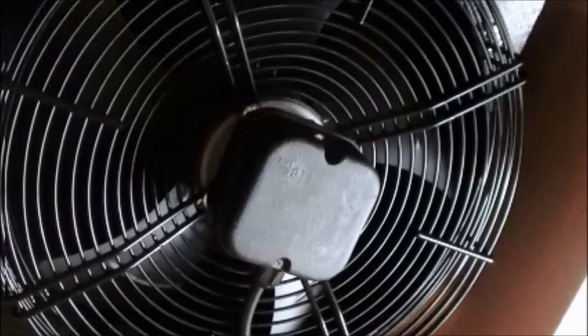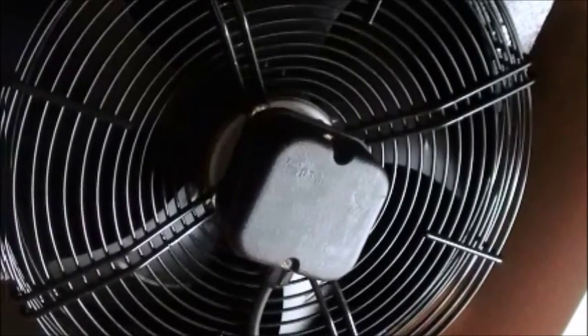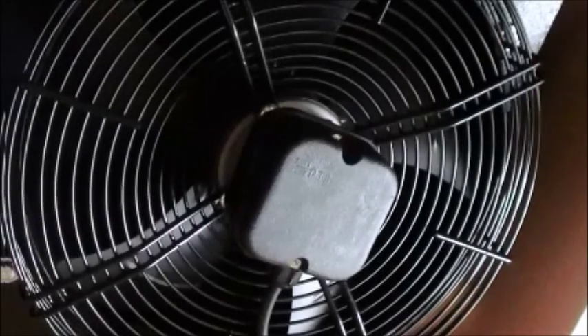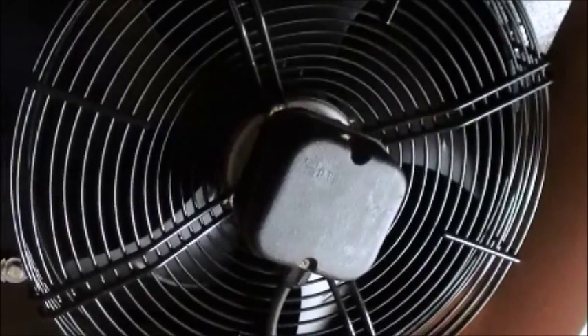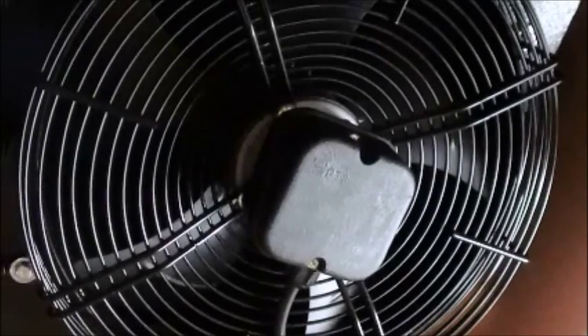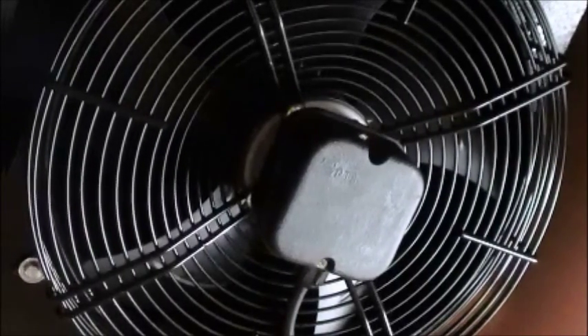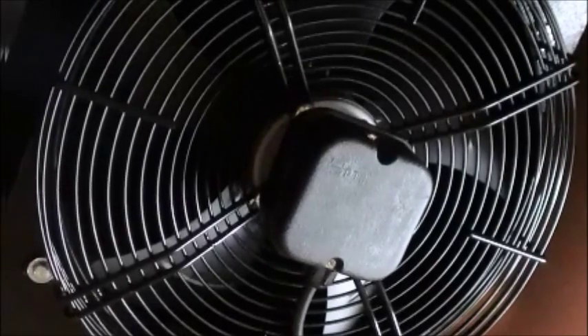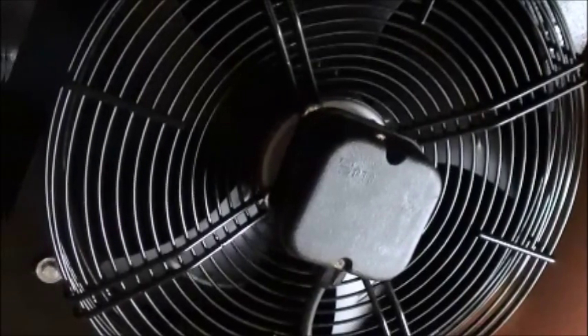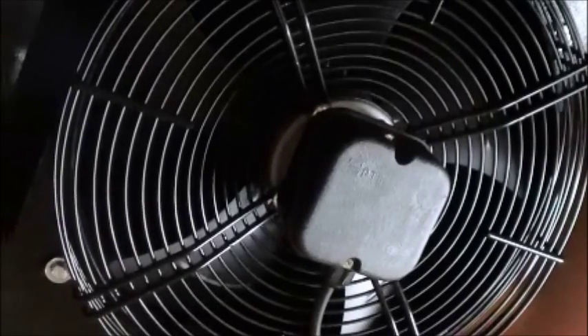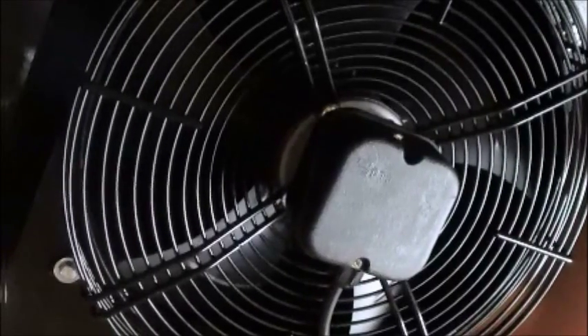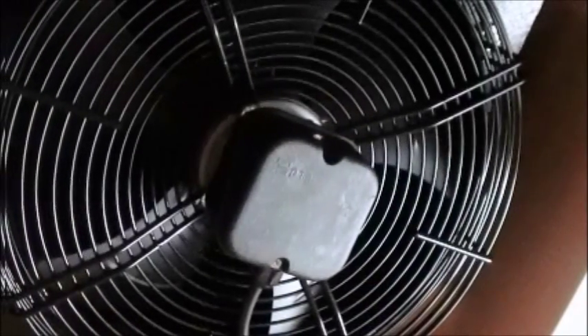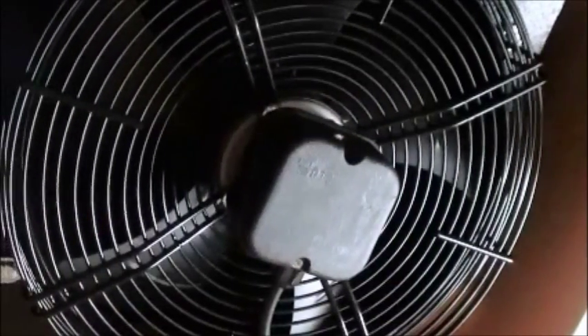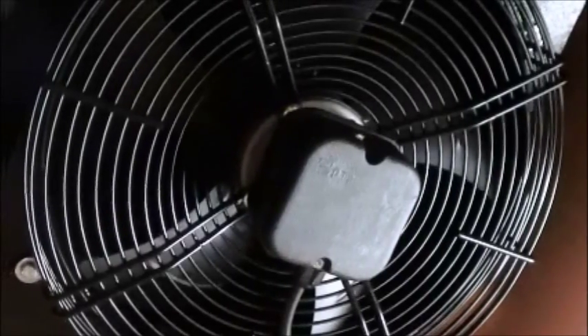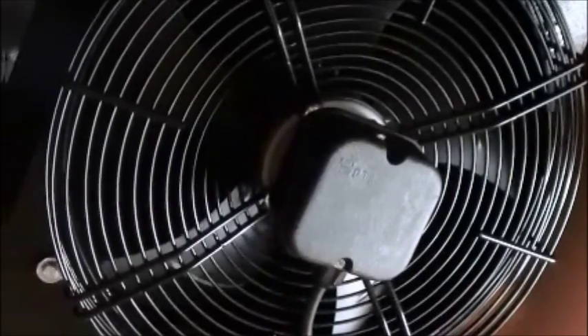The air-cooled radiator is equipped with a premium-built electric cooling fan. The master brand, German-made Rosenberg cooling fan is quiet and has a low 1750 RPM range. Large fan blades provide high-velocity airflow to the radiator core. The programmed oil temperature control is managed via the PLC, which initiates fan cycle on and cycle off when needed. The fan motor accepts multi-volt inputs such as 208, 230, and 460. A 575 volt option is available but must be special ordered.